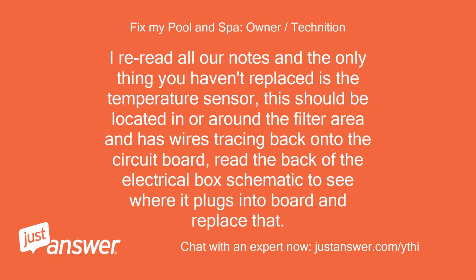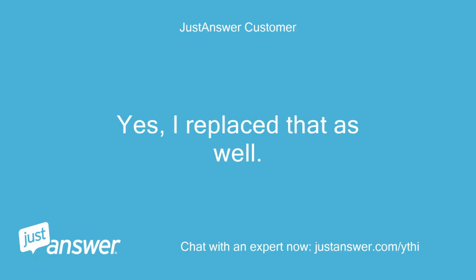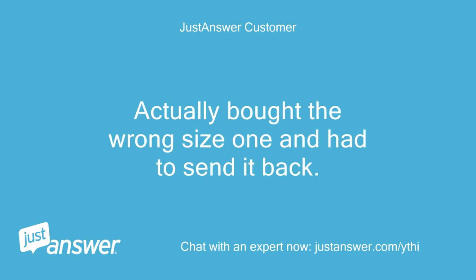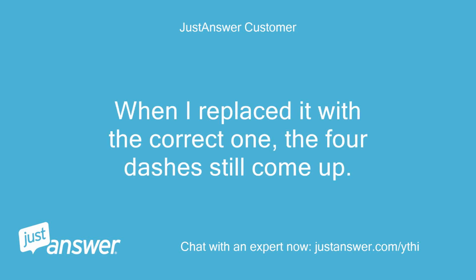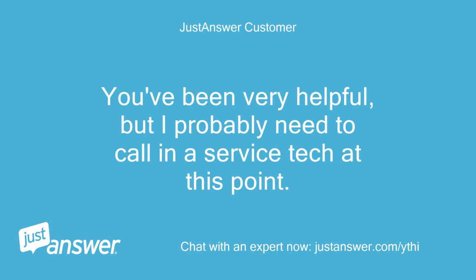I reread all our notes, and the only thing you haven't replaced is the temperature sensor. This should be located in or around the filter area and has wires tracing back onto the circuit board. Read the back of the electrical box schematic to see where it plugs into the board and replace that. Yes, I replaced that as well. Actually bought the wrong size one and had to send it back. When I replaced it with the correct one, the 4 dashes still come up. You've been very helpful, but I probably need to call in a service tech at this point. Thanks.